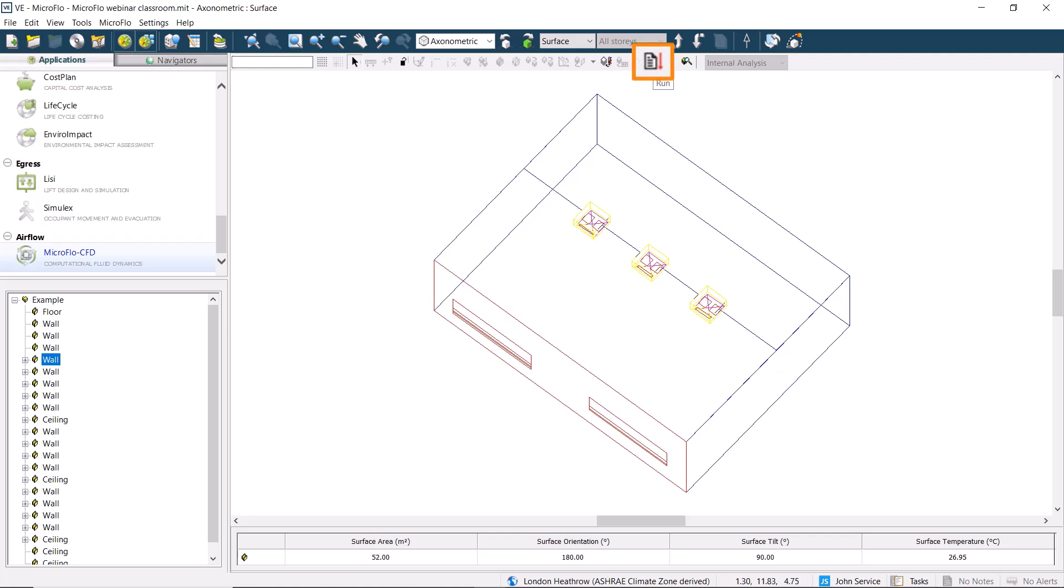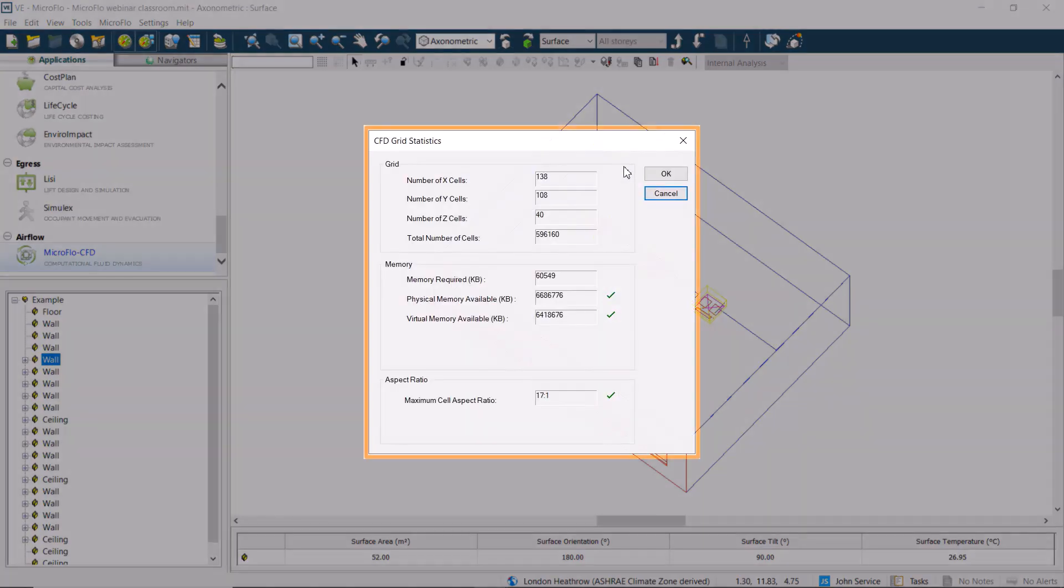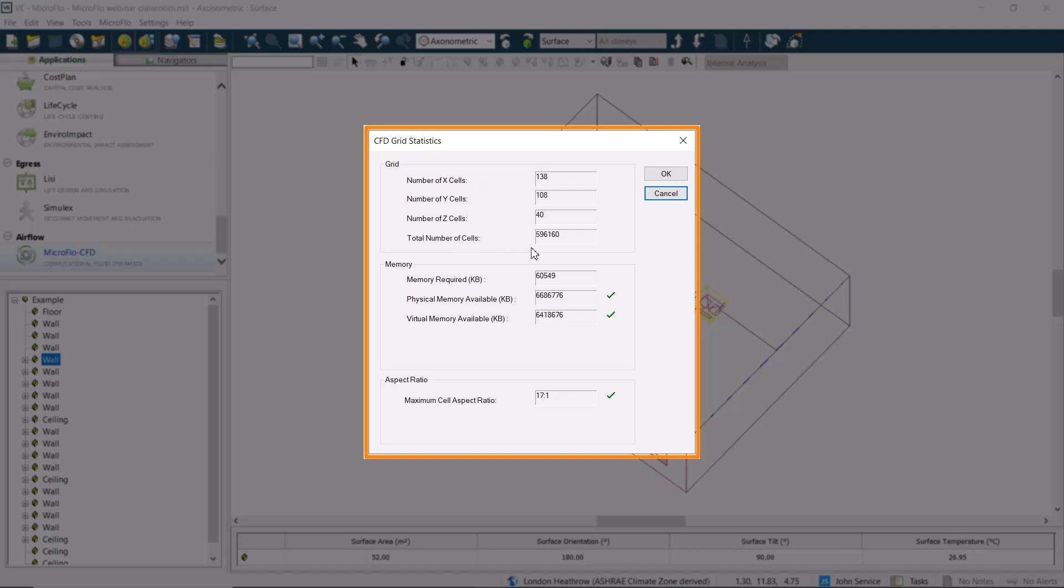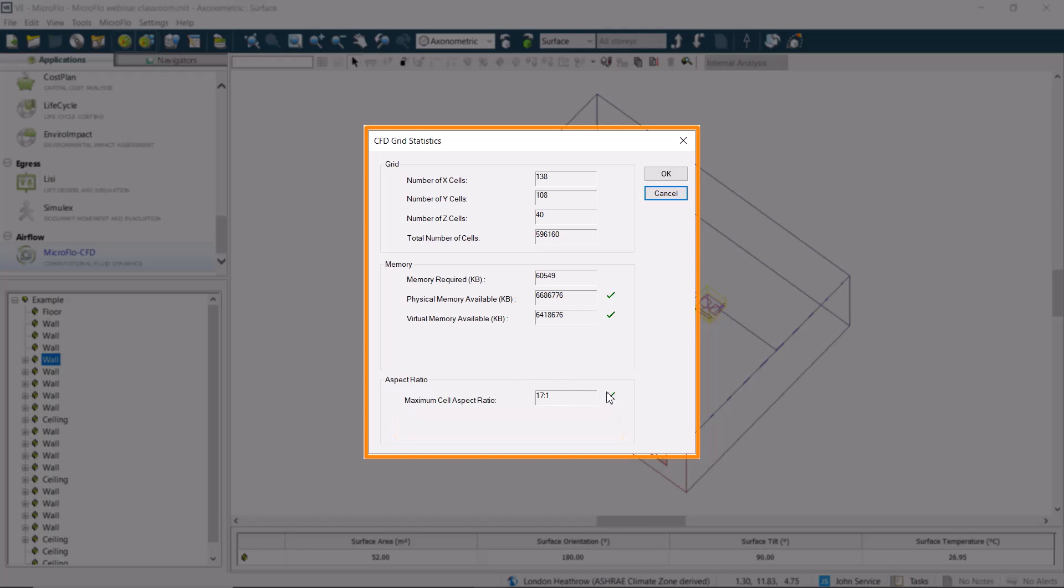Now we're ready to click on the button to run our CFD calculations. This opens up the CFD grid statistics, including the grid and the total number of cells. It's handy to check that the memory required is not too high. This is linked to the size of the model. It also shows the maximum aspect ratio, which shouldn't be too high, as this may cause instabilities, and the calculation may fail. This should have a green tick.